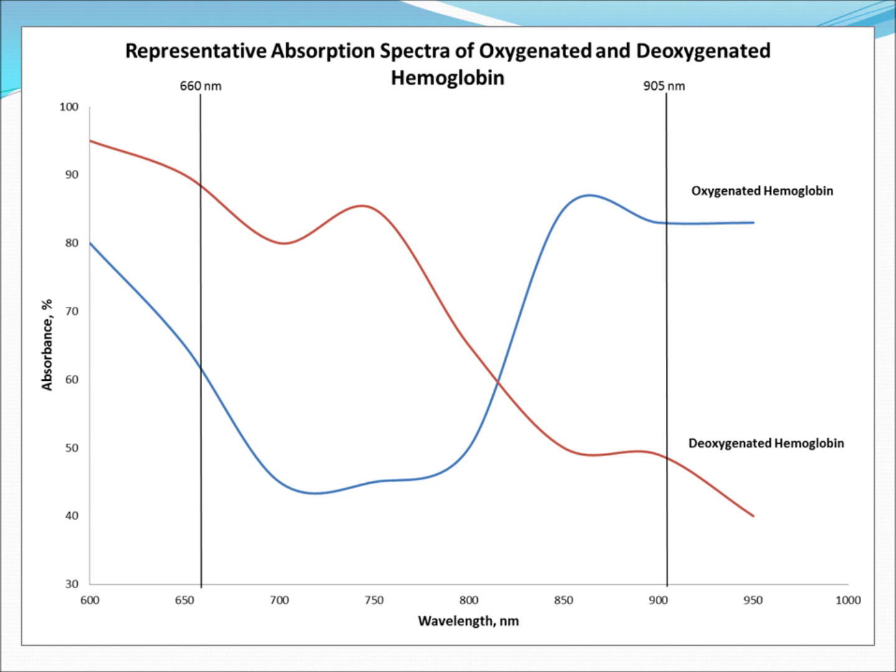Deoxygenated hemoglobin absorbs more strongly at 660 nm than does oxygenated hemoglobin. Conversely, oxygenated hemoglobin absorbs more strongly at 905 nm than does deoxygenated hemoglobin. The ratio of the oxygenated to deoxygenated hemoglobin can be determined from the ratio of the observed absorbances at 905 and 660 nm. From this information, the percent SpO2 can be calculated via an empirically determined calibration algorithm performed by the manufacturer of the instrument.